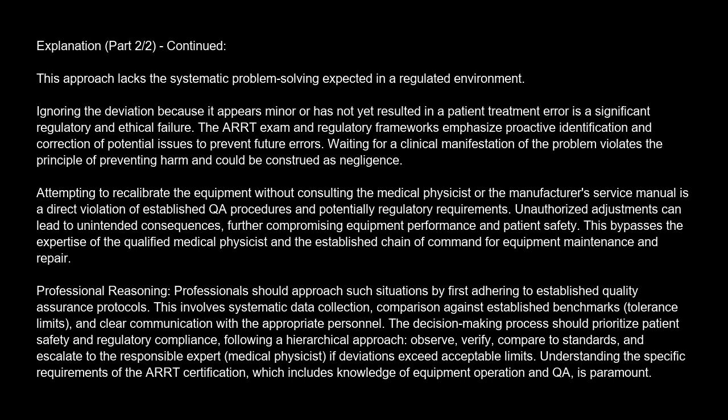Attempting to recalibrate the equipment without consulting the medical physicist or the manufacturer's service manual is a direct violation of established QA procedures and potentially regulatory requirements. Unauthorized adjustments can lead to unintended consequences, further compromising equipment performance and patient safety. This bypasses the expertise of the qualified medical physicist and the established chain of command for equipment maintenance and repair.